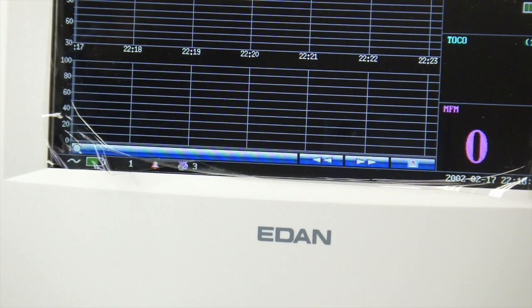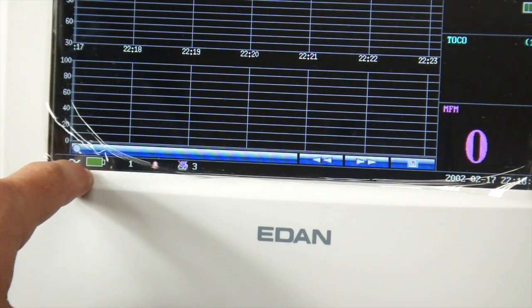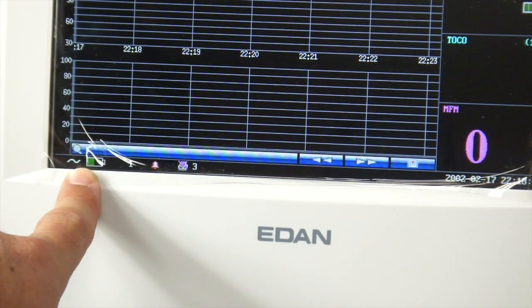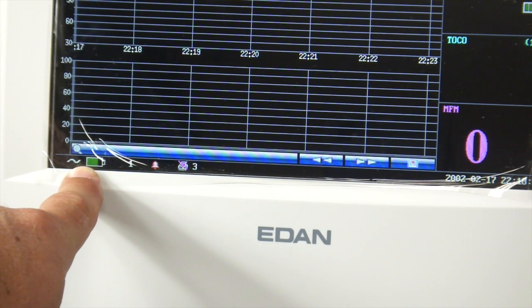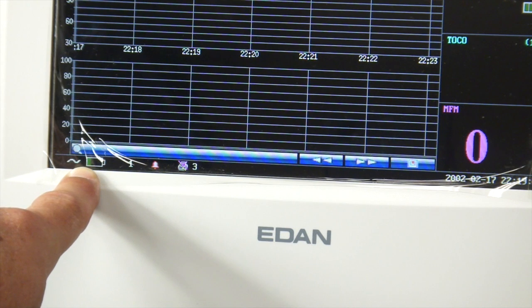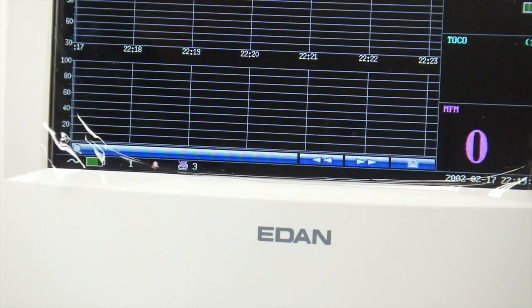If AC power were to be removed, you would get an X through that AC power indicator. The second icon over is the battery indicator. The battery indicator currently shows charging, which means it's cycling through its various stages of charge. If the battery was not present, you would have an X through the battery. And if the machine was actually operating on battery power, it would be solid green in the state of charge of the battery. So 100% charge, it would remain solid green.